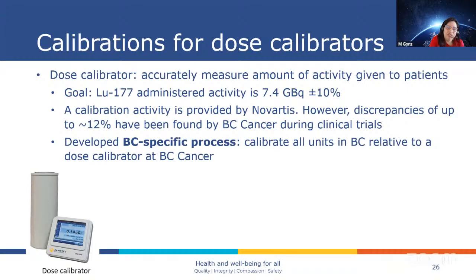Because we give 7.4 gigabecquerels plus or minus 10%. So that's the clinical allowance. You can be off by 10% of that activity, and you're still okay to give to patients. So if the activity is outside of that range, then you can't give it to patients, and you have to figure out why. So we have to calibrate that equipment to make sure that what we're reading is accurate.